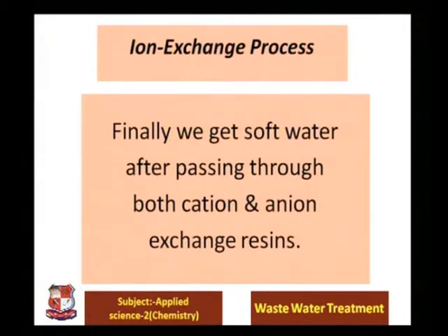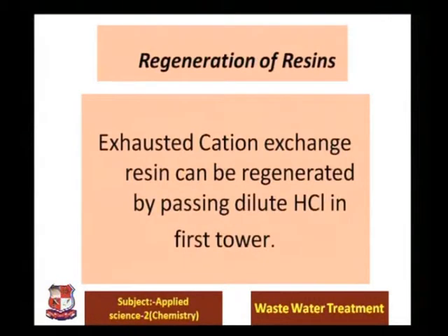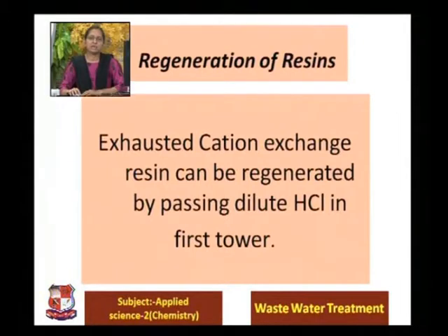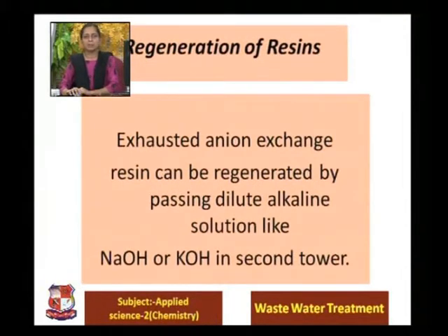These things have to be kept in mind. We have seen the regeneration. Cation exchanger resins can be regenerated by adding dilute HCl, and similarly anion exchanger resins can be regenerated by adding sodium hydroxide or potassium hydroxide in the second tower.